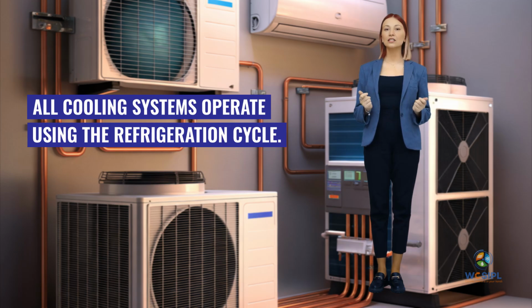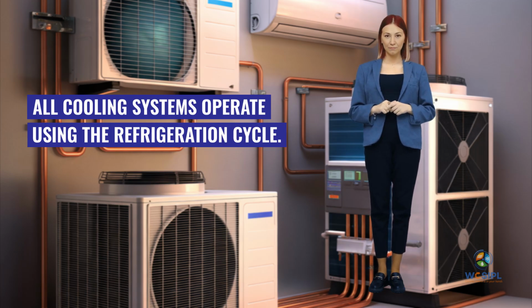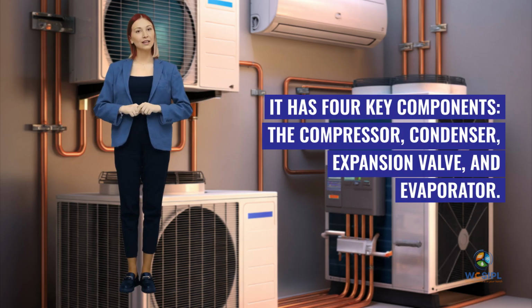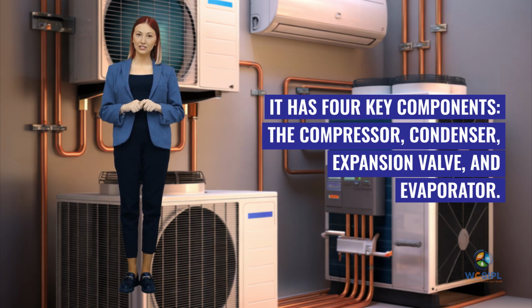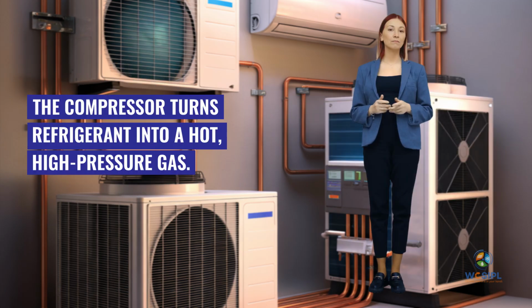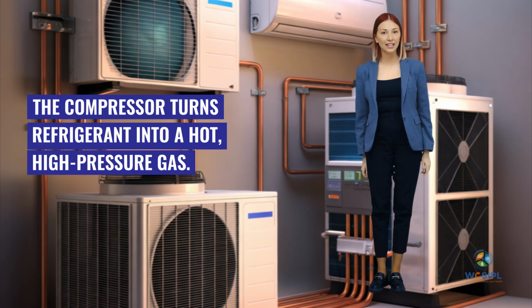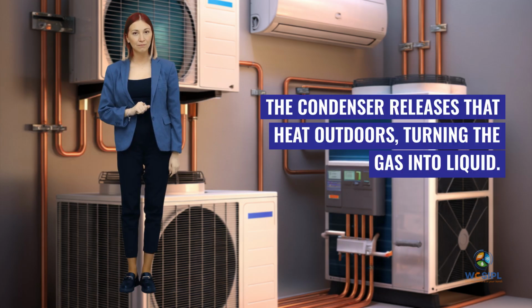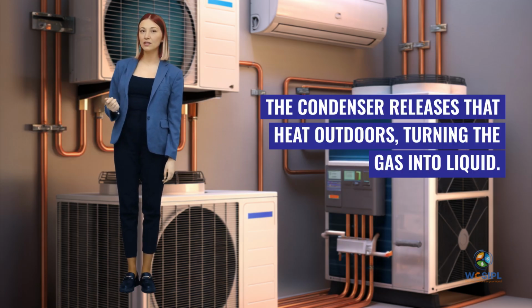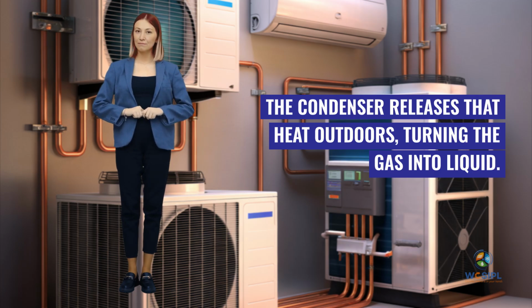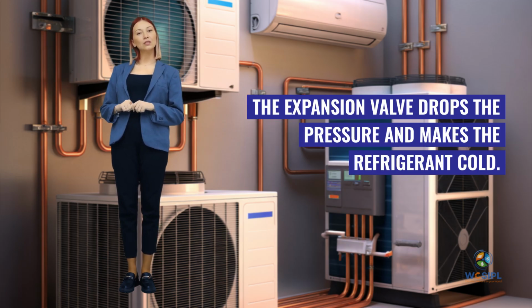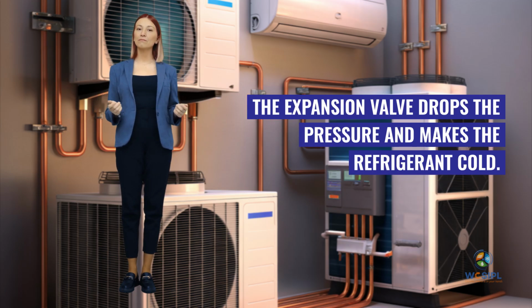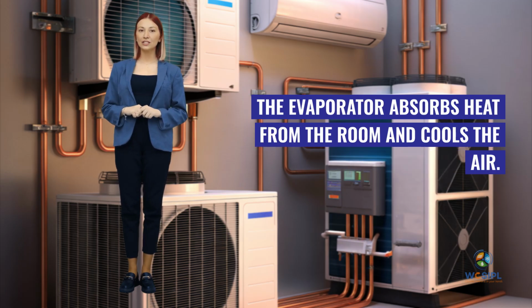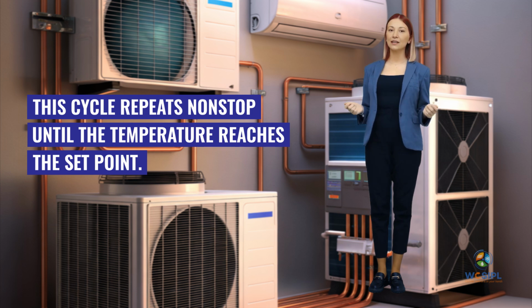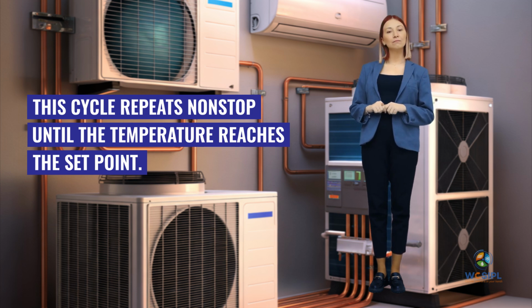All cooling systems operate using the refrigeration cycle. It has 4 key components: the compressor, condenser, expansion valve, and evaporator. The compressor turns refrigerant into a hot, high-pressure gas. The condenser releases that heat outdoors, turning the gas into liquid. The expansion valve drops the pressure and makes the refrigerant cold. The evaporator absorbs heat from the room and cools the air. This cycle repeats non-stop until the temperature reaches the set point.